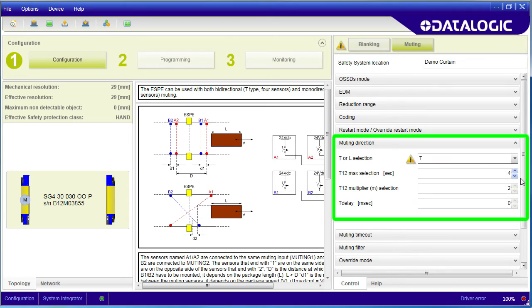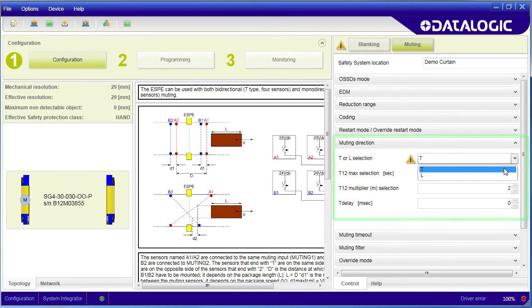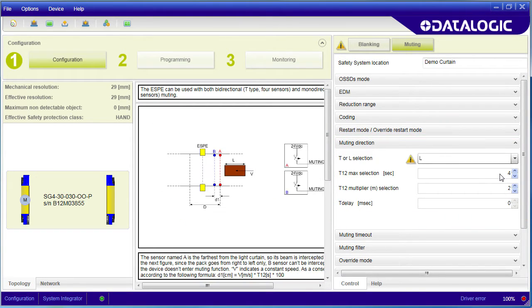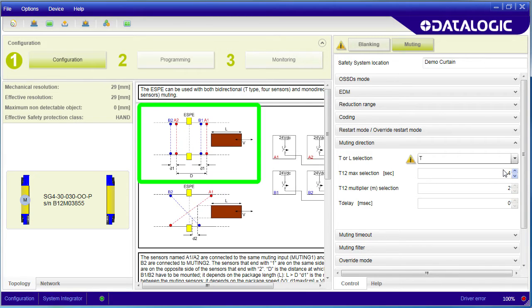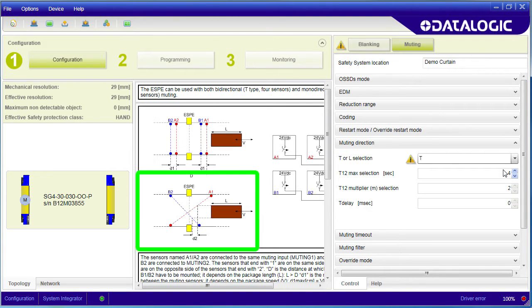Here we set the muting direction and to do that we need to specify the configuration – T or L. L is simple – you have a pair of sensors. Given those two inputs, the light curtain can determine the direction and speed of the approaching object. The T configuration can be setup like a double L or like this so it can detect objects coming from either direction.